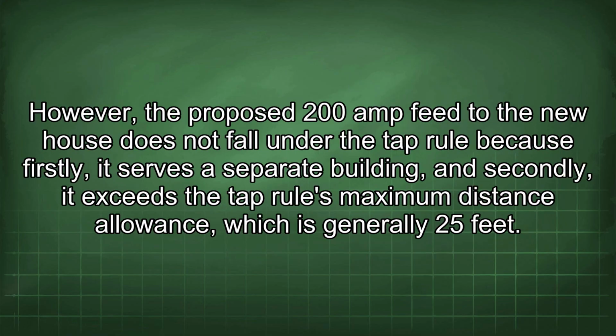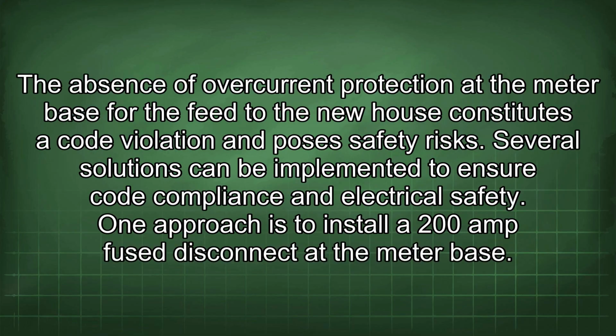However, the proposed 200 amp feed to the new house does not fall under the tap rule because, firstly, it serves a separate building, and secondly, it exceeds the tap rule's maximum distance allowance, which is generally 25 feet. The absence of overcurrent protection at the meter base for the feed to the new house constitutes a code violation and poses safety risks. Several solutions can be implemented to ensure code compliance and electrical safety.